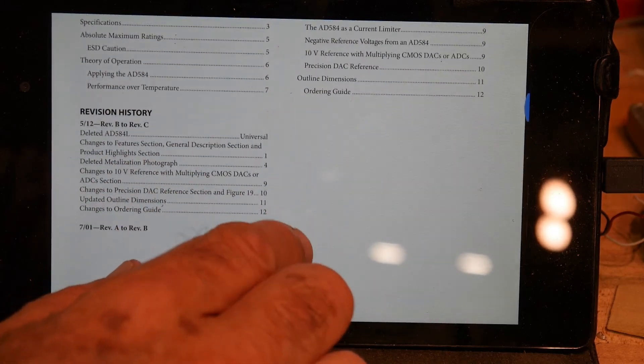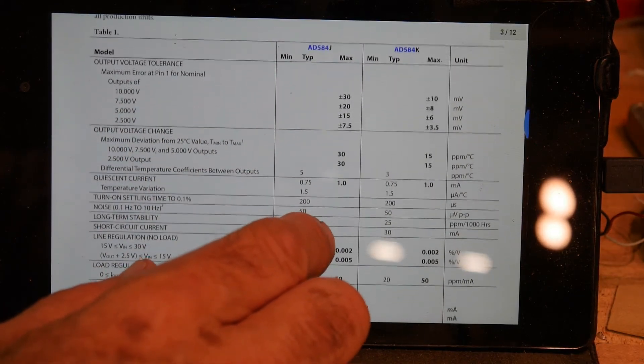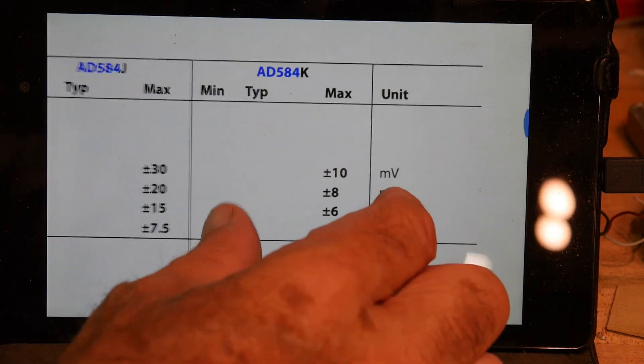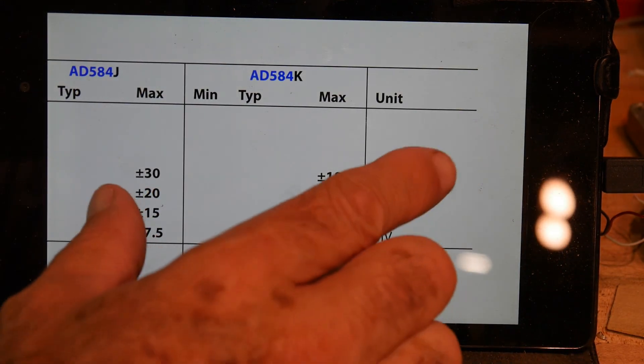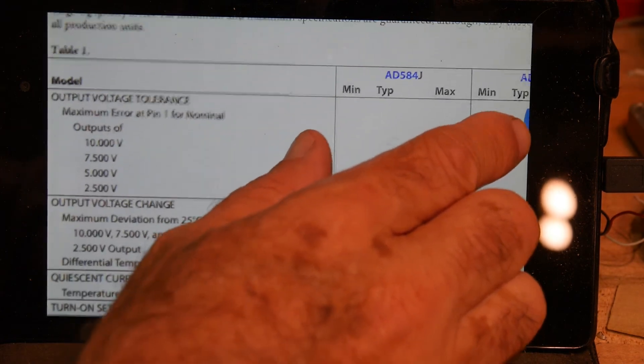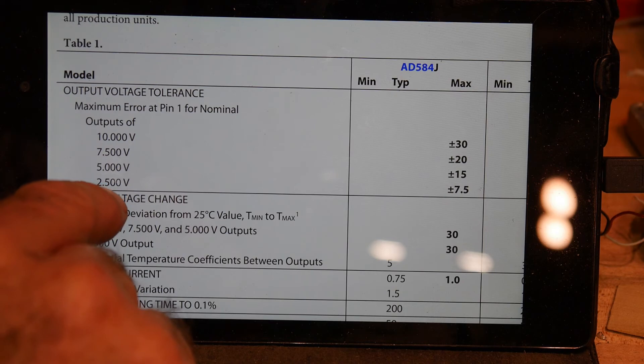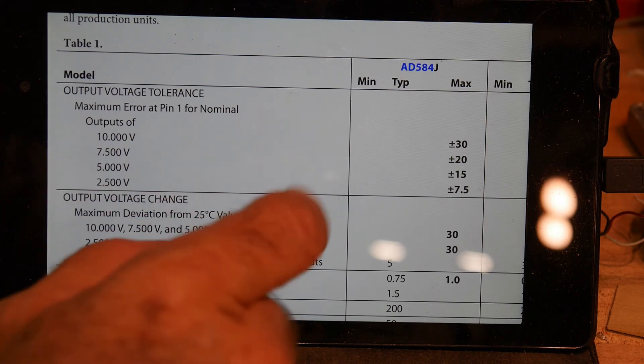And what we're really interested in is how accurate is it. Like I said, it's very stable. These are the K versions. So it basically can output 10 volts, 7.5, 5, and 2.5. That's what we saw on the little box.